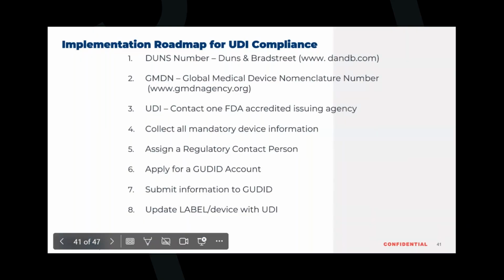All device labelers must obtain DUNs or DUNS numbers as they are used to identify the organization and GUDID. RSC can obtain these numbers for you. A device labeler is required to identify the global medical device nomenclature code for each device identifier. UDIs have a device identifier and a production identification number. The DI must be issued by an FDA accredited agency, determined by production information, such as the lot number. A separate UDI is needed for every version of each device.